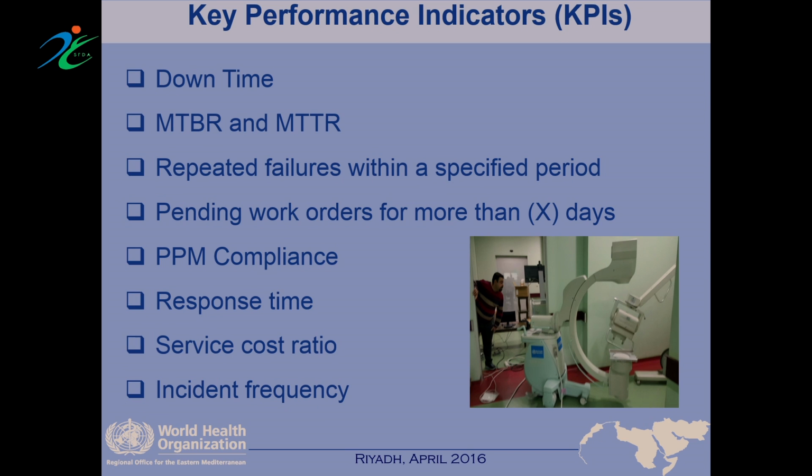If I have planned to do PPM for a piece of equipment 2 times a year or 1 time a year, then at the end of the year I'm going to go back and check those data to confirm which were implemented or not implemented. So this shows how I'm doing the work, and then how many pending orders I have over a year, for particular days.